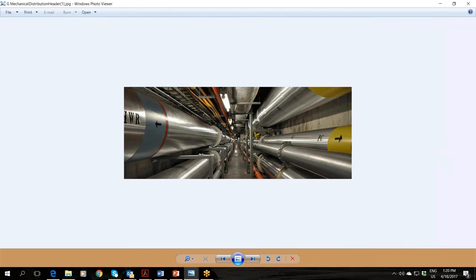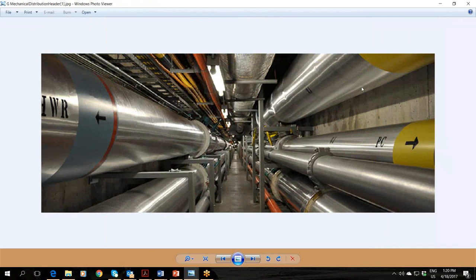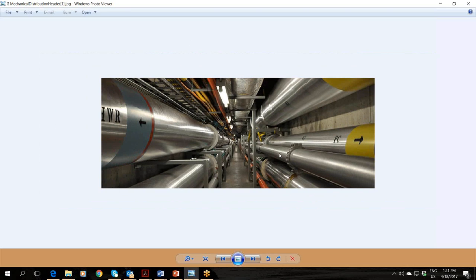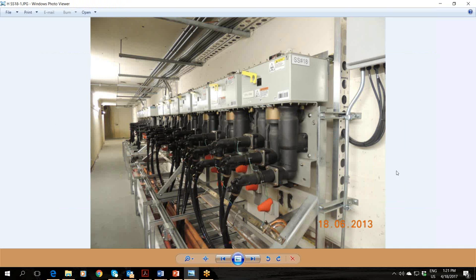Just another photo of a bunch more cables. So this is a picture of our services corridor. It's a big honking rectangular concrete bunker under the ground of the campus, and it connects all these different buildings together. You can see the vast majority of it's taken up by piping infrastructure for chilled water, for steam supply and condensate return, all those kinds of things. And you can see the medium voltage cables just up here. It's not a confined space, because it has HVAC units and there are air changes. So it's basically like a building underground.